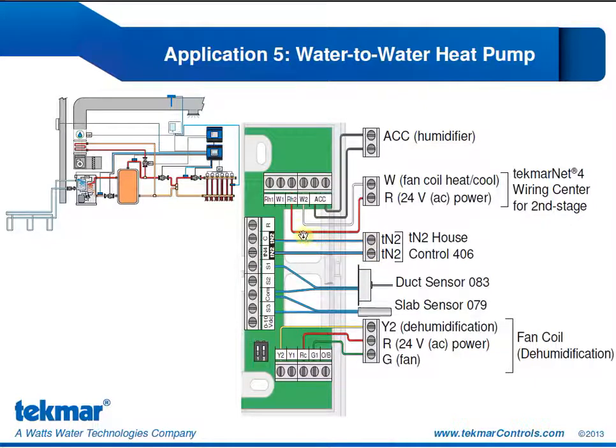Taking a look at our wiring. Because we're connected to a TN2 house control, we have our TN2 connections from the 557 to the house control. Our second stage of heat, the fan coil, we have to bring the RH2 and W2 connections over to a tekmarNet 4 wiring center, to the R and the W on the wiring center. Our accessory relay is controlling the humidifier as shown in the ductwork.